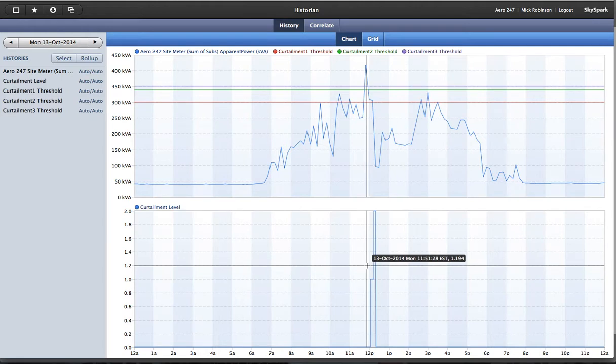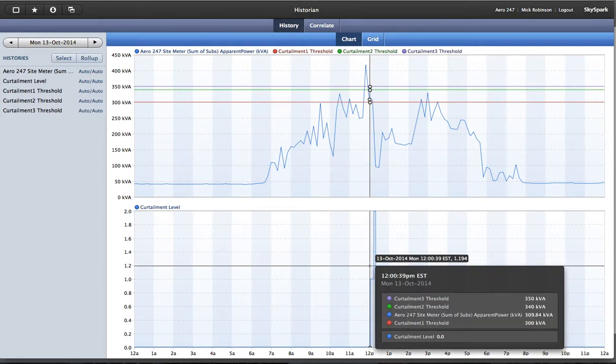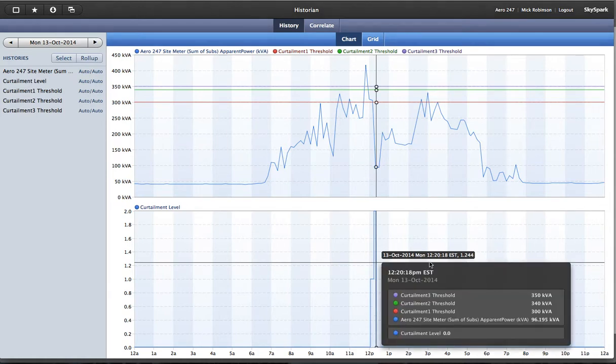And you can see there, the whole thing started at 12 o'clock and then ended at 12:20. So for roughly 20 minutes there were changes within the HVAC. No occupants within the building made any complaints during this time, so it was a very effective curtailment with no impact to the occupants.